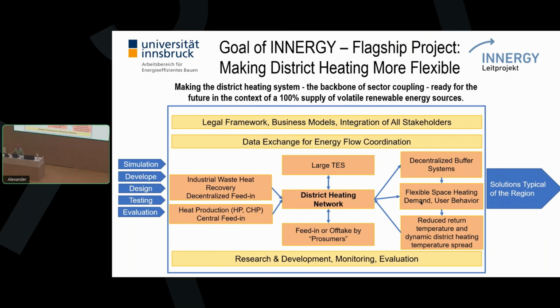So this is a lot of possibility we can use for increasing the flexibility. And what is an important point for district heating: reduced return temperature and dynamic district heating temperature spread to increase the efficiency of district heating, to reduce heat losses, but especially to increase the power, because power in a district heating system is flow rate multiplied with temperature difference. And if I have only a small temperature difference, then I need a lot more flow rate. And if I have a large temperature difference, then the flow rate can be much smaller. Pump electricity is much less, and the pipe dimensions are much smaller, so a lot of advantages.